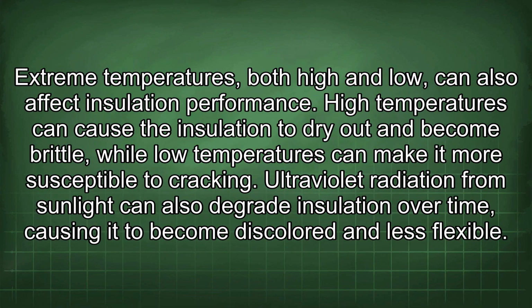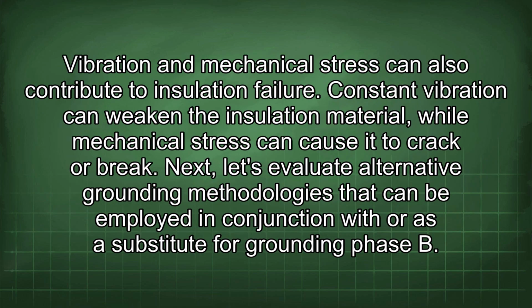Extreme temperatures, both high and low, can also affect insulation performance. High temperatures can cause the insulation to dry out and become brittle, while low temperatures can make it more susceptible to cracking. Ultraviolet radiation from sunlight can also degrade insulation over time, causing it to become discolored and less flexible. Vibration and mechanical stress can also contribute to insulation failure. Constant vibration can weaken the insulation material, while mechanical stress can cause it to crack or break.